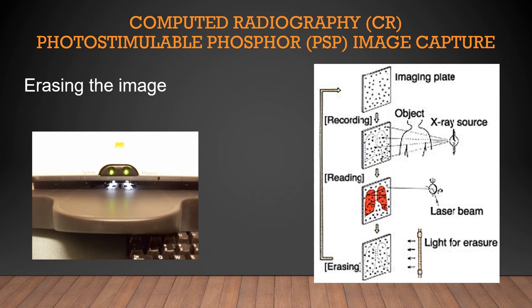Now, when I was performing mammography, we would do some imaging with the cassettes where we would take like 20 exposures on them, and then we would erase them. Sometimes I would have to erase them many times because those images wouldn't go away. That was a special thing that we did. So if you erase it and then go to take an x-ray and you see that there's still some residual, you probably have to keep erasing it several times.